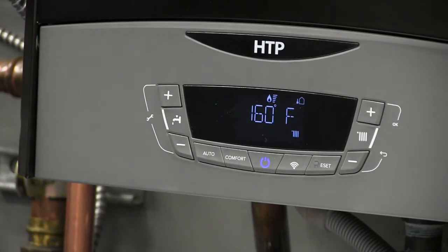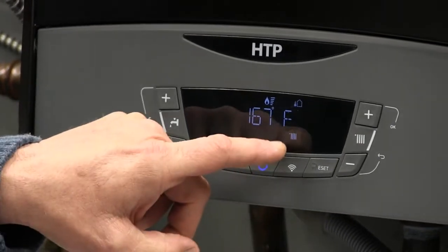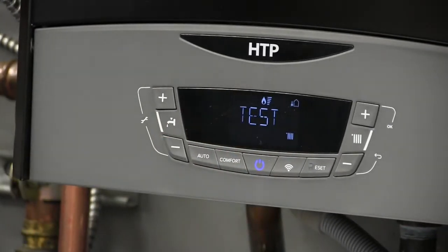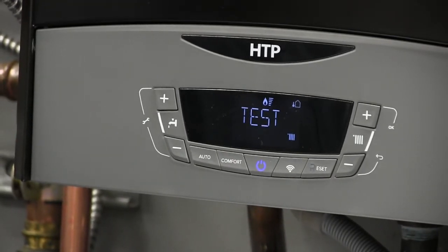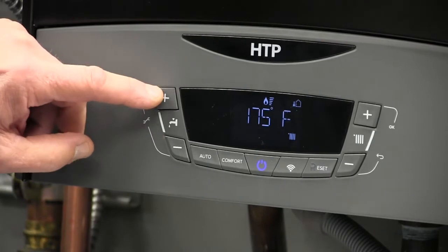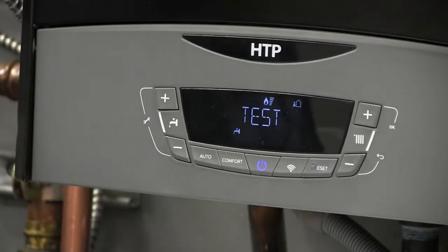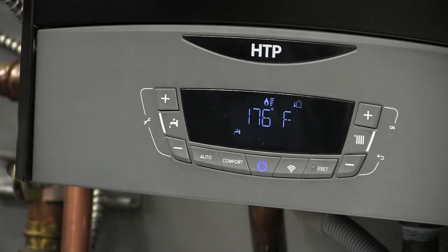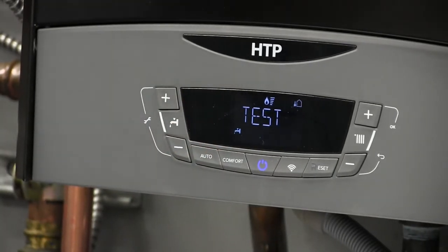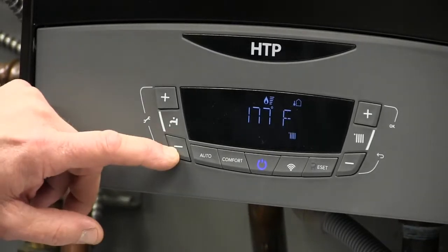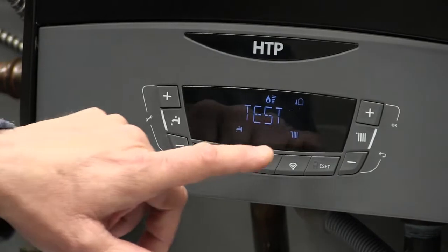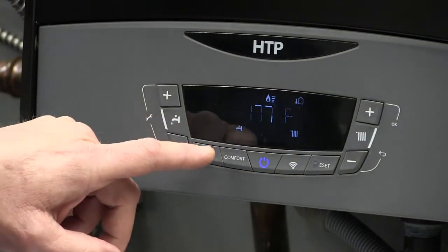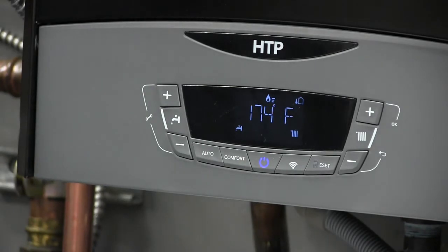The burner will fire, and currently, to know where we are, we can see the central heat icon, which would let us know that we are on central heat high fire. If we hit the plus button, we now notice the domestic hot water faucet icon. This tells us that we are in high fire for domestic hot water. If we hit the minus button and go down 2 steps, we will see the domestic hot water faucet icon and the radiator icon. This indicates that we're in low fire. Low fire is shared by both DHW and CH.